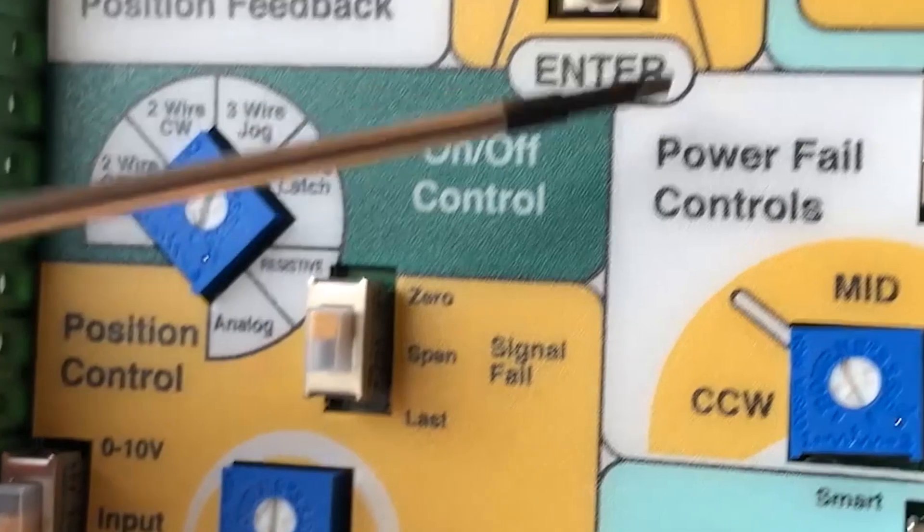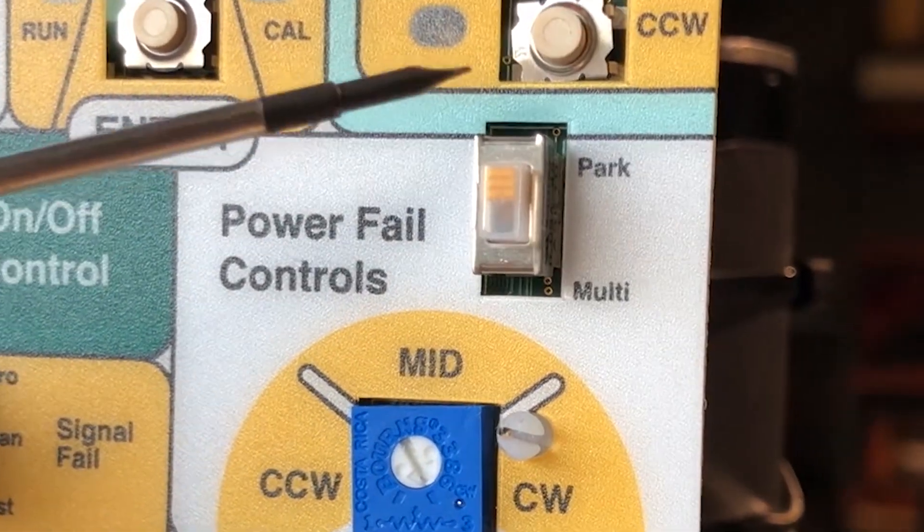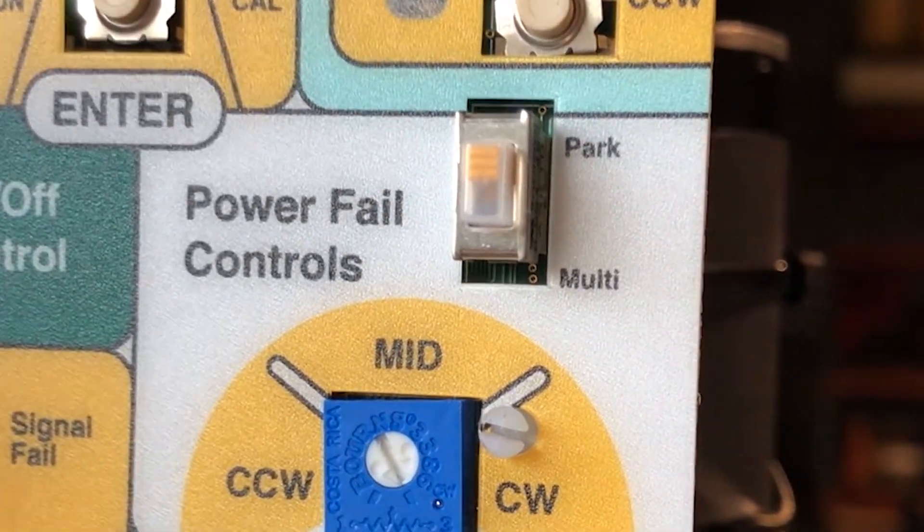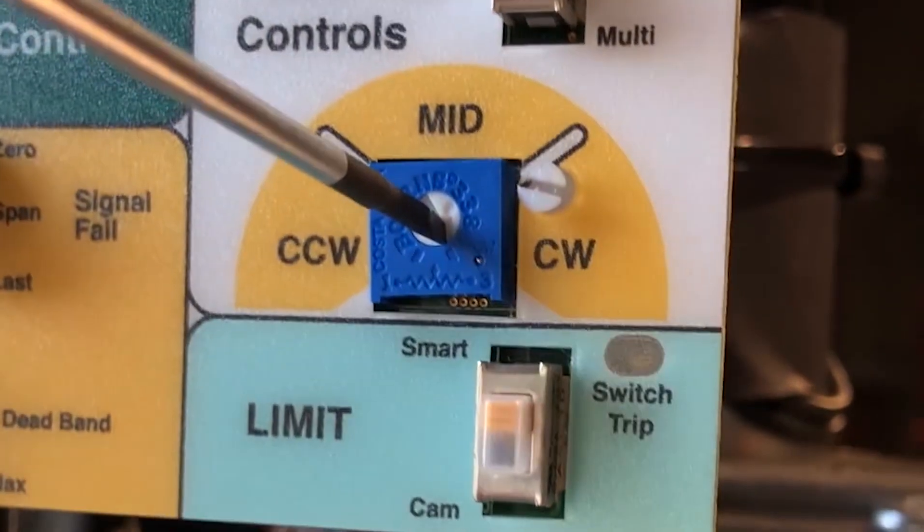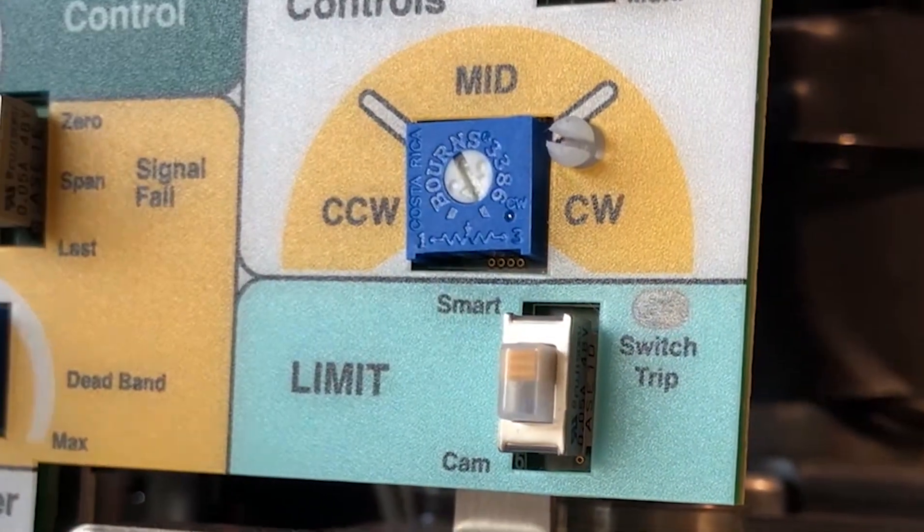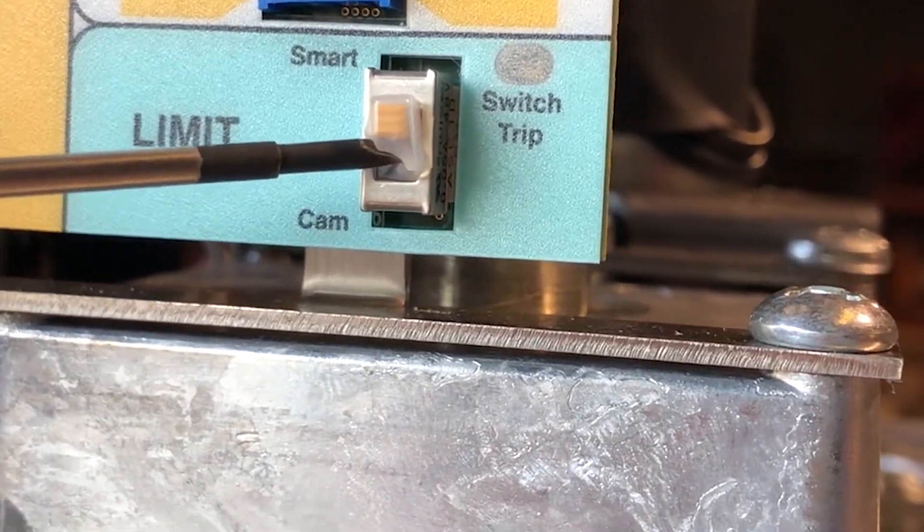Coming over here to your power fail controls. This is where you want your valve to end up if a loss of power. Go to the park position and in this demonstration I'm going to park it in the counterclockwise position which is in the closed position. Limit you want to be in the smart position.